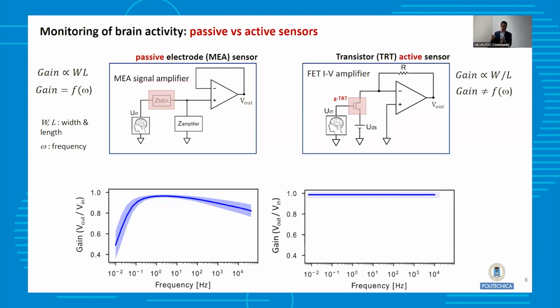On the other hand, there is another concept, which is for active electrodes, which are a transistor. It's a device that has two terminals, and the conductivity of the transistor changes when the electric potential in the vicinity changes. That's an active device. And because of the electrical coupling between that device and the amplifier that you use for measuring, it allows you to measure down to very low frequencies. So passive electrodes have a drop in the gain at low frequency, and active electrodes don't.